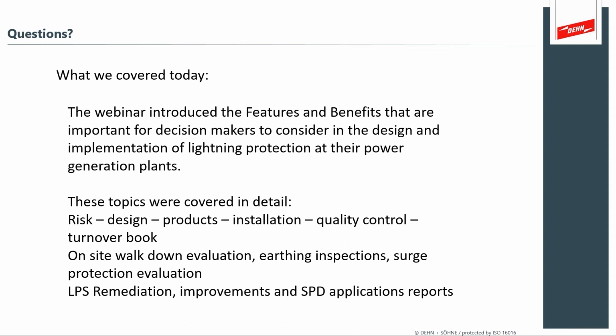Yes. So on the stacks that we design the lightning protection systems for, these are generally lower than 60 meters. And we would do the entire rolling sphere calculation, including the stacks, and make sure that they are protected. But if we look at what the requirements are in the standard, if a structure is less than 60 meters tall, the standard mentions that the probability of strikes to the vertical sides of these structures is really low, so they do not need to be considered. But we do the rolling sphere for the roof and all the horizontal protrusions around these structures to make sure that they are protected.